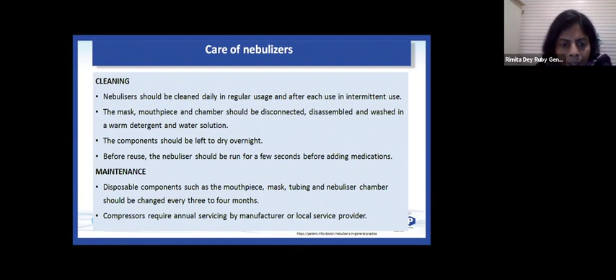Before use, the nebulizer should run without medicines for a few seconds, and then you add medications. That actually helps to blow away any of the dried particles of detergent or other things that can harm your patient. Disposable components such as mouthpiece, mask, tubing, and nebulizer chamber should be changed every 3 to 4 months, and the compressors require annual servicing by the manufacturer or by the local service provider. Failure to do this can definitely result in nosocomial pneumonia.